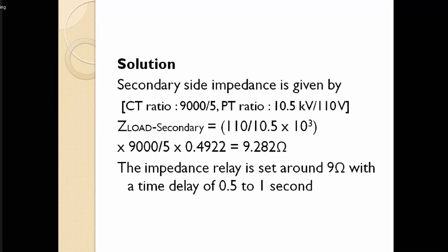It's not simple, it's technical, but it's not more technical. So these are the two things, the distance relay and the impedance relay, you can use to protect your generator. Apart from the abnormal conditions like frequency and out of step, these are the major protection schemes you are going to see in your generator. Any question?